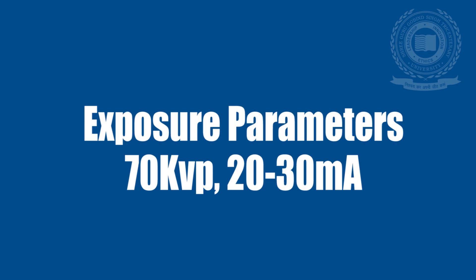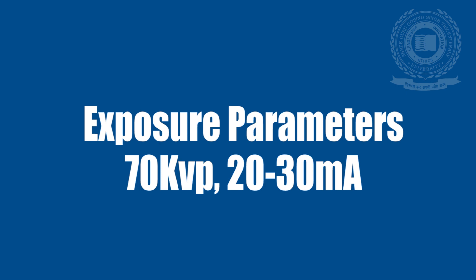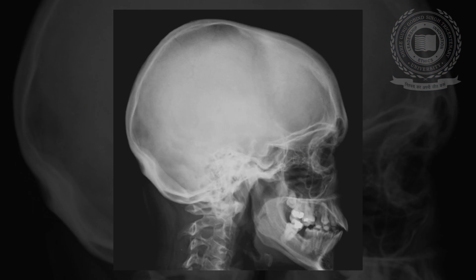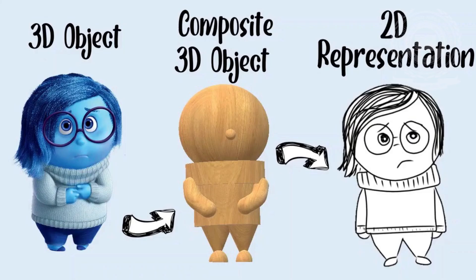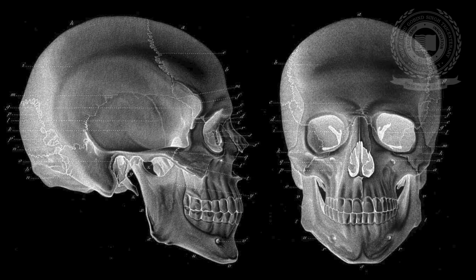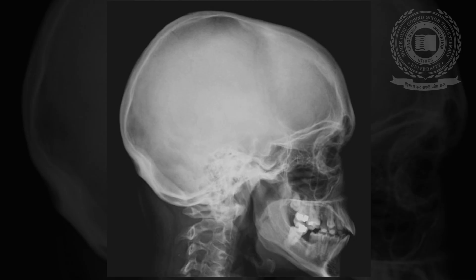The exposure parameters that can be used are 70 kV and 20 to 30 mA. The resultant image is a conventional two-dimensional representation of the lateral aspect of the skull with superimposition of the right and left halves. Structures closer to the image receptor are less magnified than structures located closer to the x-ray source, so some discrepancy in the superimposition of both sides is always evident.